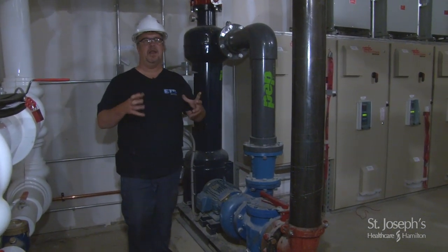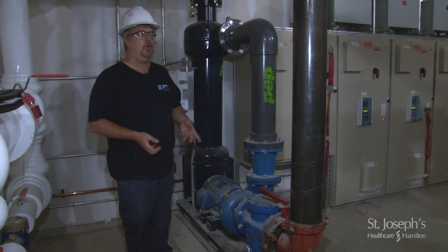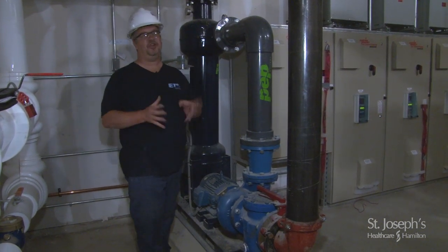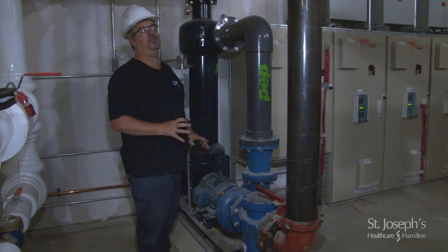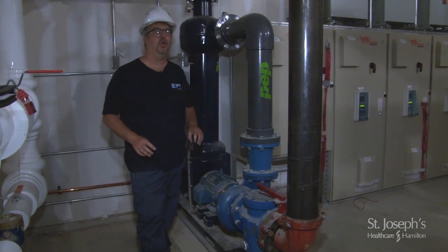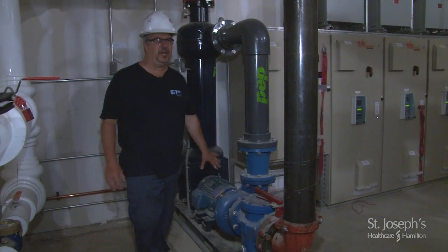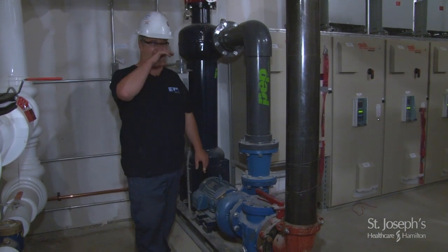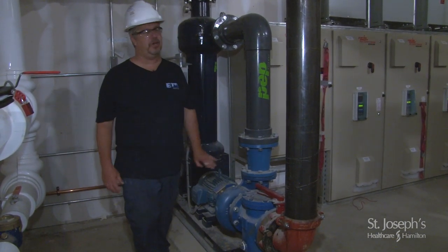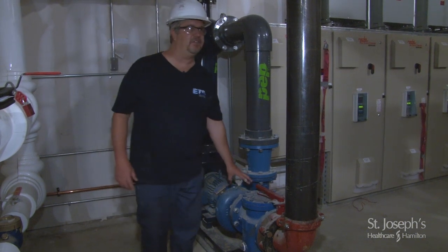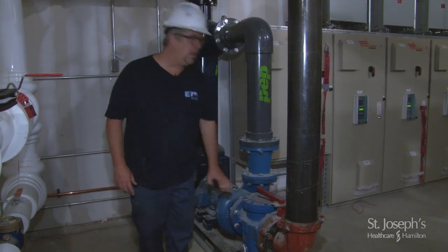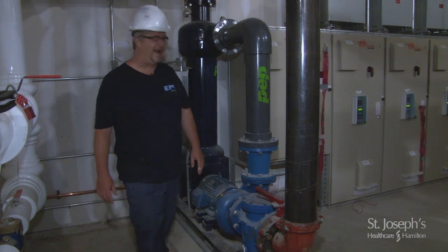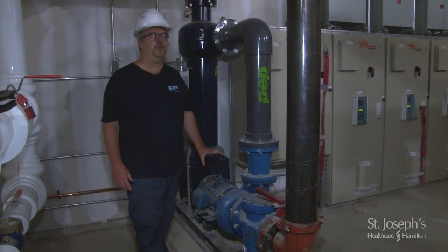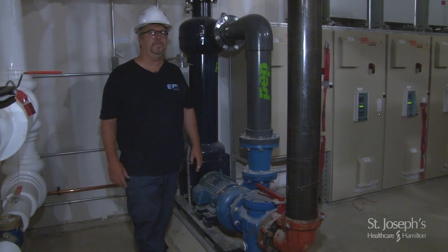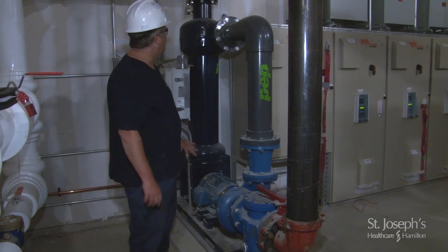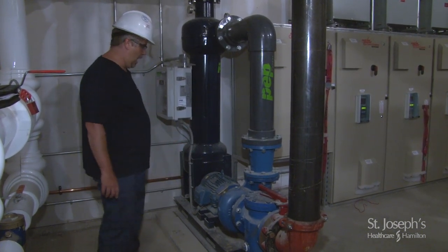Inside there you're going to find a basket filter. What that basket filter will do is catch and trap any large particles that might be coming through the system before they actually get dragged into your pump and cause damage. The very first thing you should check is that that's clean. That probably on a normal operation of the tower is something you may only have to do on an annual basis. Beyond that, the unit is fully automatic.